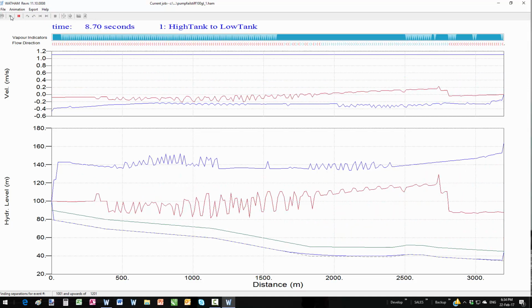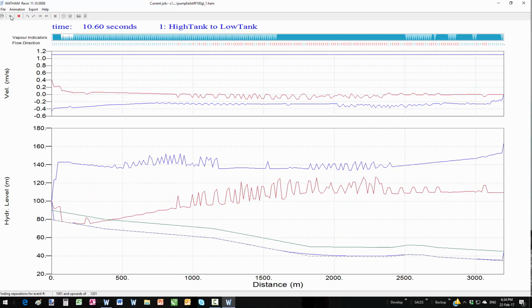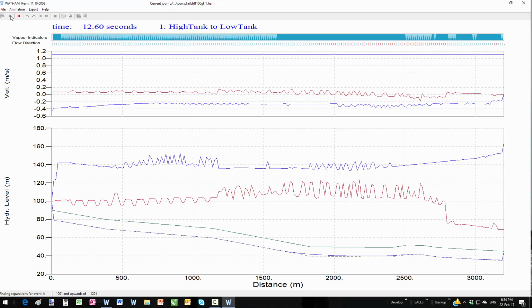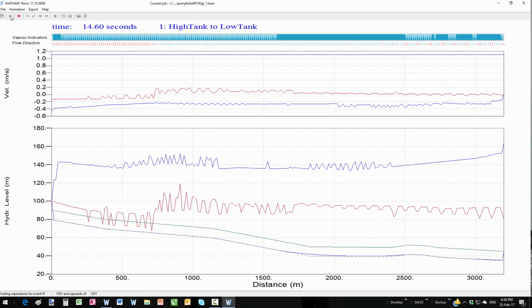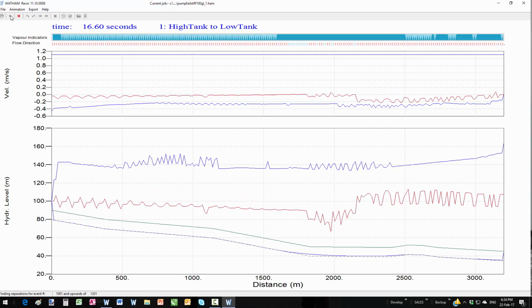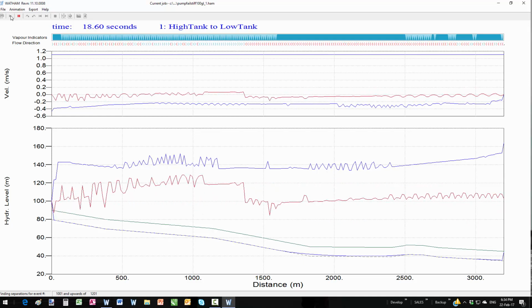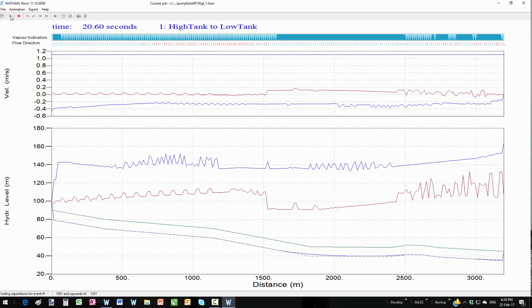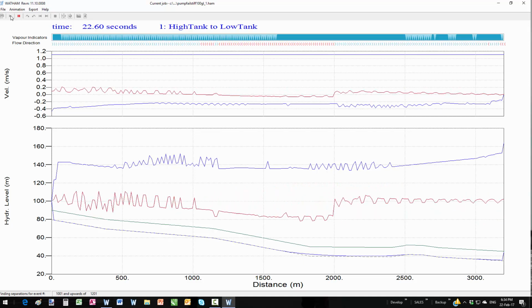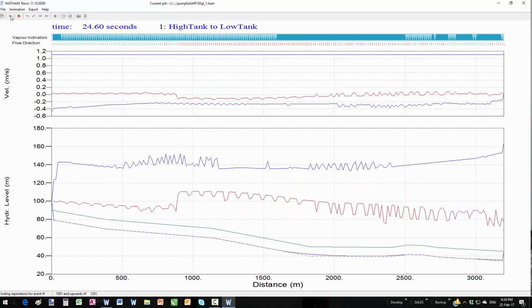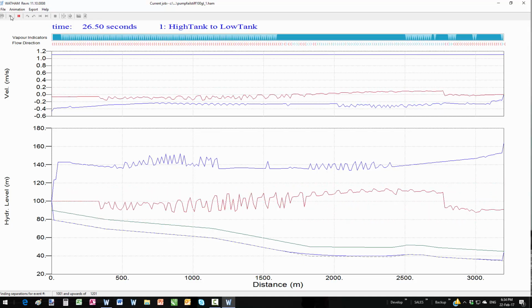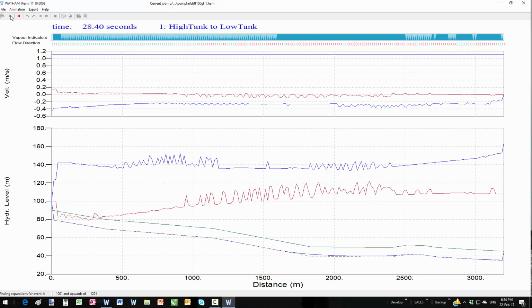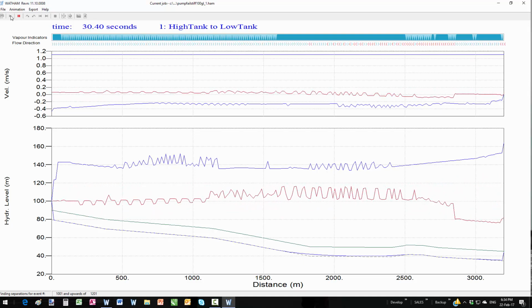we can now see that separating the water column with vapour pockets, which later collapse and recombine into a single water column, totally changes the transient behaviour of the system. The dynamics of the water column is changed dramatically. It is important to understand that vapour head of water at normal ambient temperature is about -10 meters.